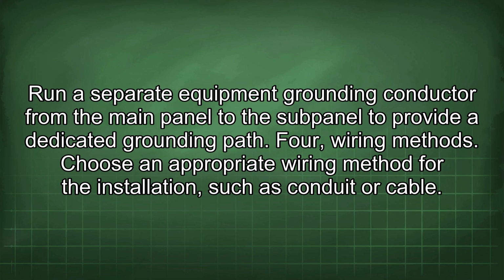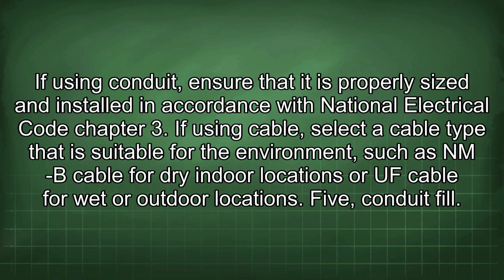4. Wiring methods. Choose an appropriate wiring method for the installation, such as conduit or cable. If using conduit, ensure that it is properly sized and installed in accordance with National Electrical Code Chapter 3. If using cable, select a cable type that is suitable for the environment, such as NM-B cable for dry indoor locations or UF cable for wet or outdoor locations.